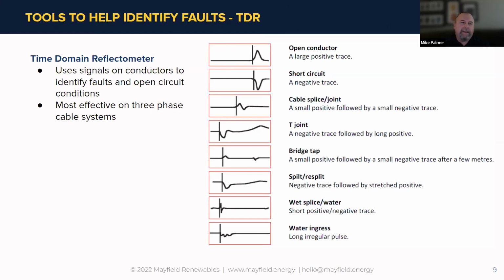Telecom, cable TV, and electrical, as you mentioned, especially three-phase cable. But what we see in PV is that distribution side, or that DC side, going from the module, from the strings back to the inverter, is typically a one conductor cable. And what TDRs do is they send a low voltage pulse into the cable under test, which is typically two metallic paths, and they look for any impedance change within the cable. And if they see that change, they reflect it back in the way of a trace on the screen that you're seeing on your screen right now.